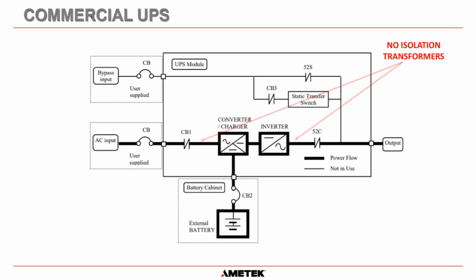And if you don't have those isolation transformers, then the DC inside here has a reference to ground. So in some circumstances, depending on the design of the commercial UPS, if you go and work on this battery here and you measured between the positive terminal and ground, you may actually find that there is AC that is getting through the charger. And it could be as high, if the charger is phased fully on, it could, in theory, be as high as 400 volts, 480 volts AC to ground if it's fully on. But in some circumstances, because the SCRs aren't going to be fully on, or the diodes aren't going to be fully on, it may be about 200 volts, but it is going to be AC, and it is an electric shock hazard if you don't have an isolation transformer here.